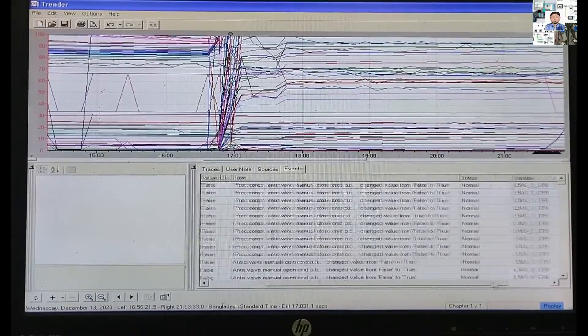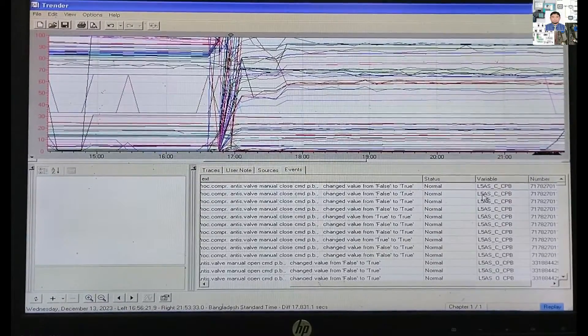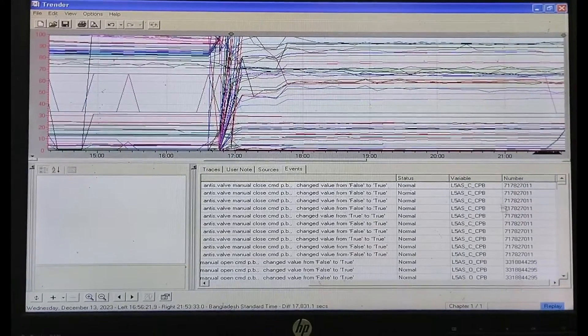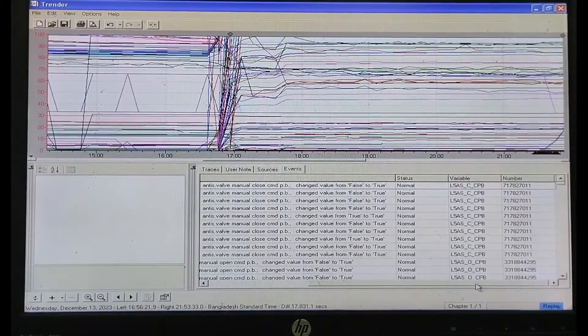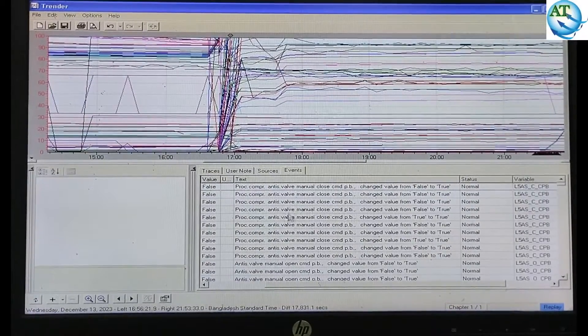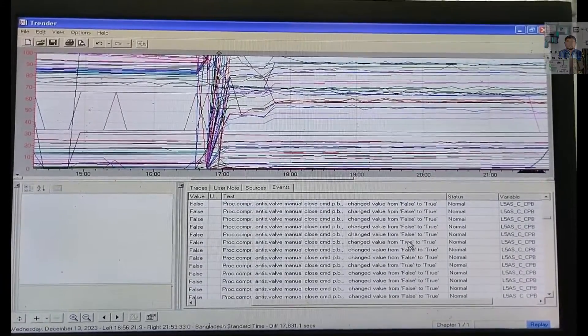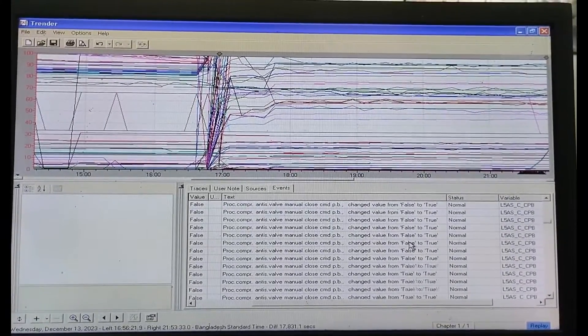Now go to the right-hand side — it is straight and showing normal. The events are showing normal. We need to find out the root cause. We go scrolling to the far side. Slowly you can scroll and find out the TRIP alarm or the main cause or the main alarm.